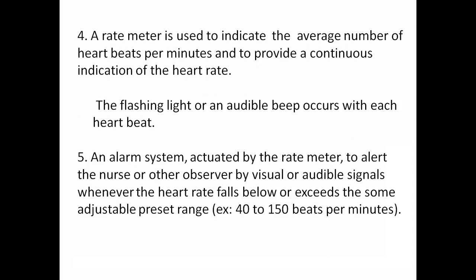If the rate meter produces a value below 40 or above 150, it will cause some problems. Any excess of this range of the heartbeat will be informed to the nurses or the observer in the form of alarms.